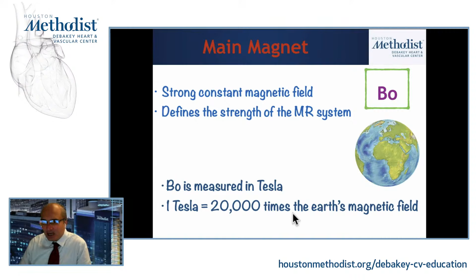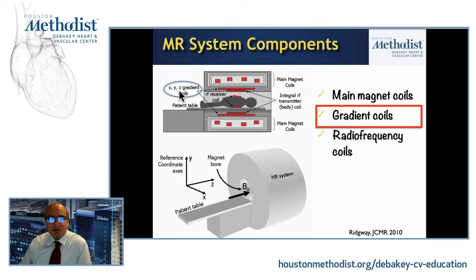Now, the next component is the gradient coils, and there are 3 sets of gradient coils, in the X, Y, and Z directions. The main purpose of these gradient coils is to cause a slight alteration to the local magnetic field, but to do it in a graded fashion. So, for example, if you have a gradient coil that causes an alteration in the magnetic field in the Z-axis, then as you get further and further away from isocenter, it will cause a more positive or more negative alteration to the magnetic field. And this is also a function of the scanner hardware itself that you purchase. So this is one of the parameters.